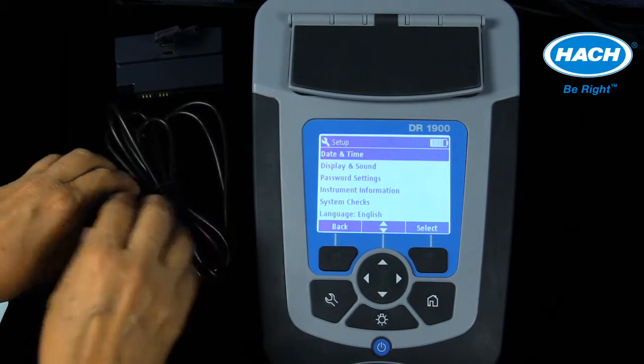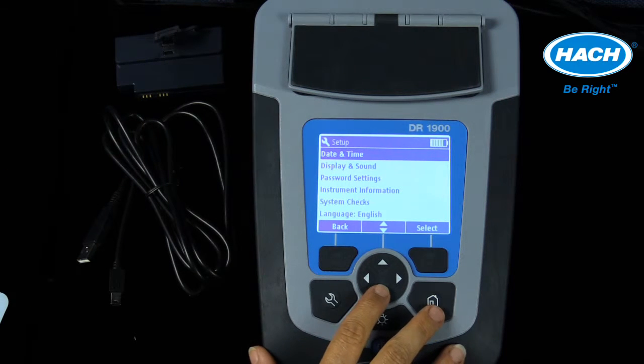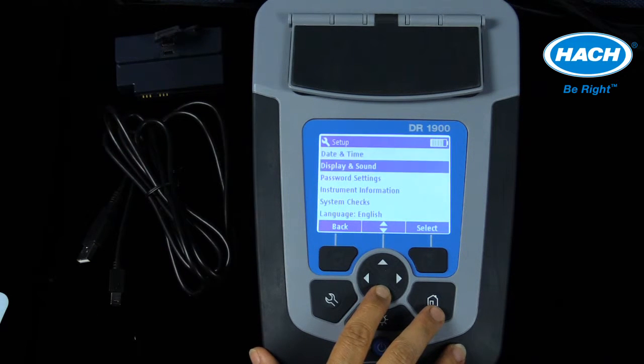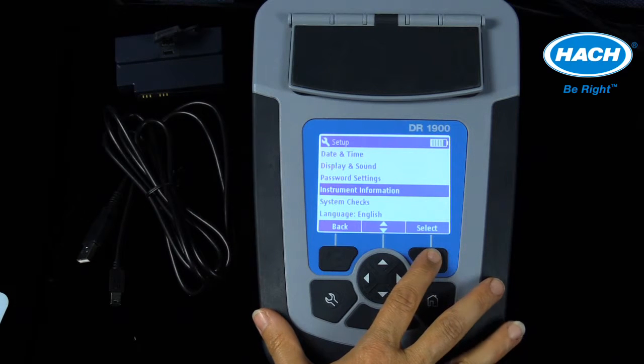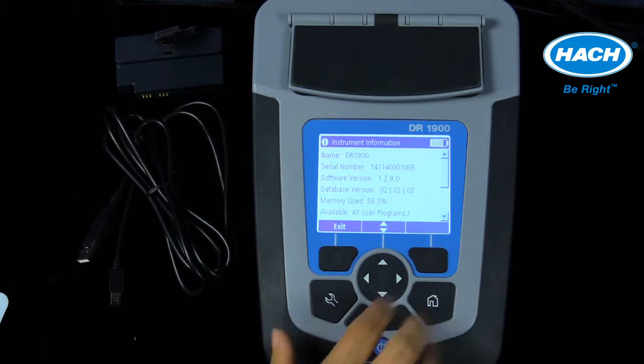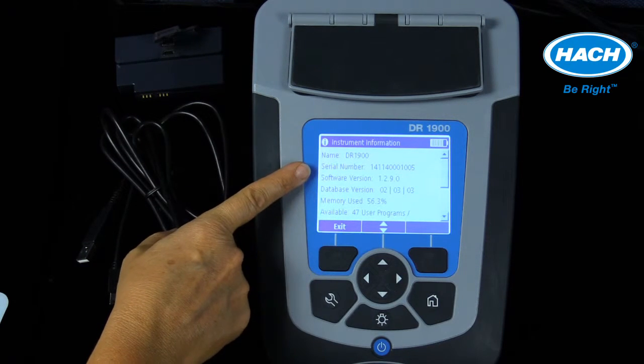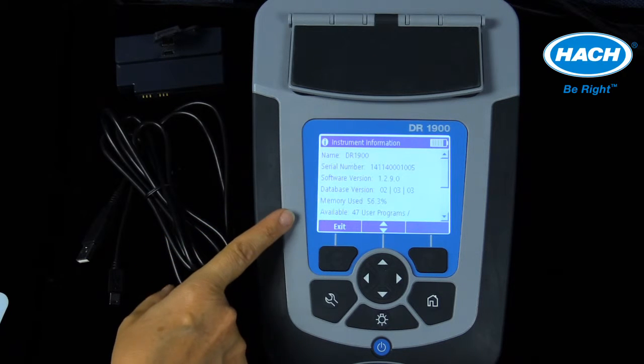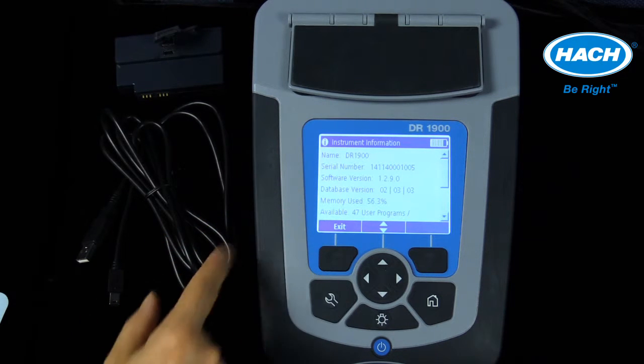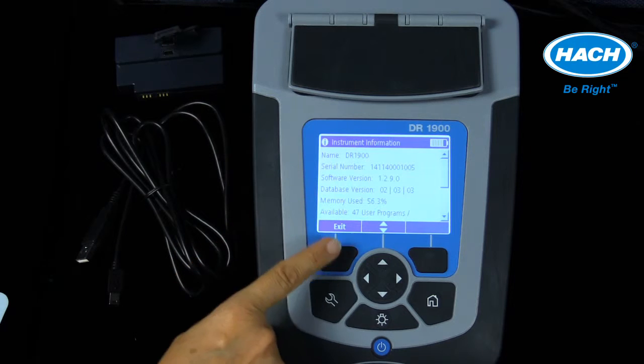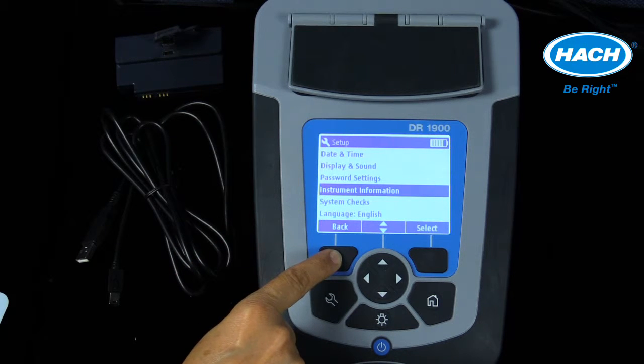To find the current software version loaded on the instrument, select the wrench key in Setup from the Settings menu. Select Instrument Information from that menu. Record the software version displayed in this menu. It will be necessary to compare this version with the Hach.com website to see if a software update is necessary.